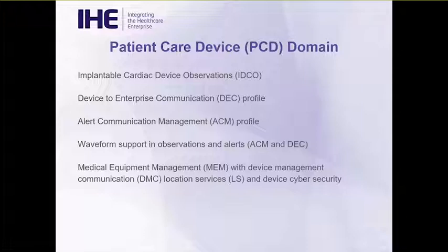MEM, or Medical Equipment Management, has two different flavors associated with it we'll cover. With device management, there's a focus on equipment used in the care of the patient, because just as well as the patient, the equipment needs to stay healthy too. This includes delivery of content and upgrade management in conjunction with computerized maintenance management systems, or CMMS.